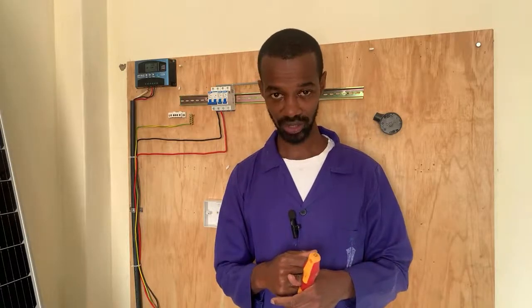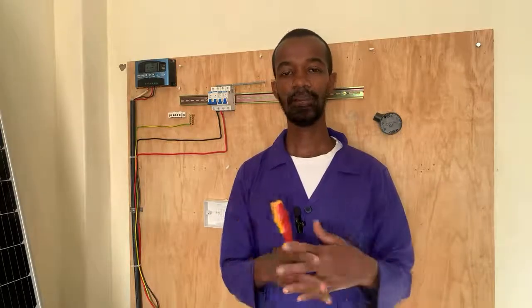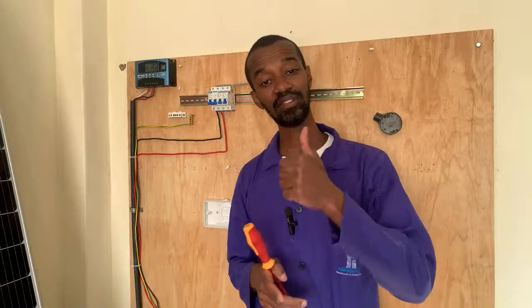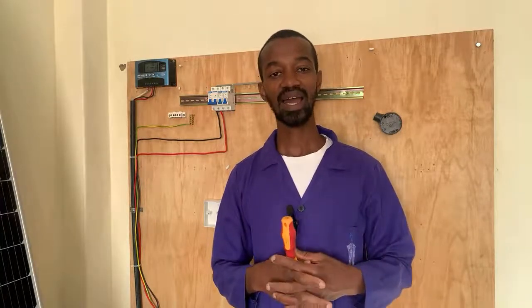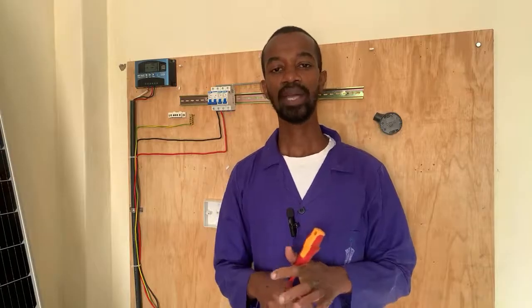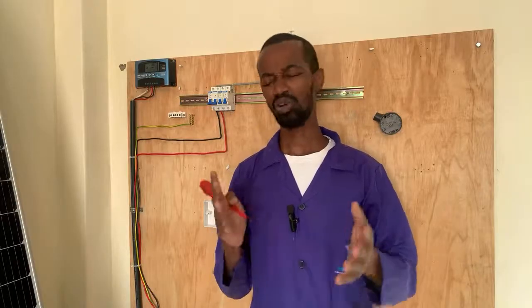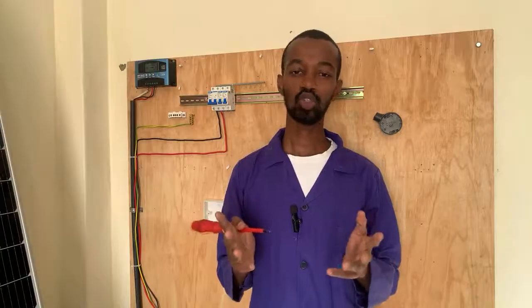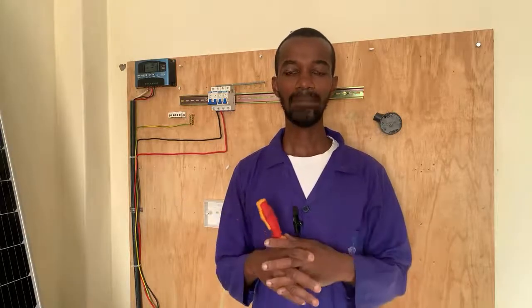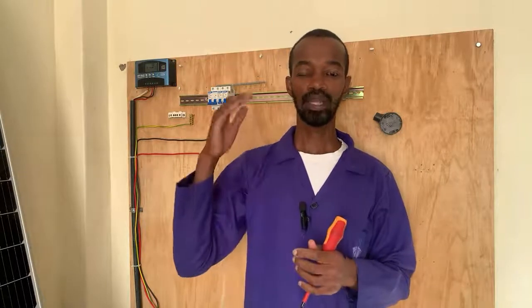these particular machines. And when it comes to, let's say, phase balancing, there are places you find that you will require a three-phase supply, but the appliances there are single phase. Now this is where your expertise at phase balancing comes in, whereby you have, let's say, first floor, second floor, third floor. All of these floors have single phase machines. All of these floors probably are on average, or they consume almost the same quantity of electricity. Now that is where your expertise in load balancing comes in, whereby you will say that this particular floor I will serve it with red phase, this other floor I will serve it with blue phase, the other floor I will serve it with yellow phase.